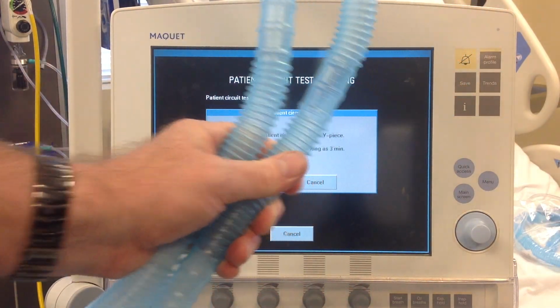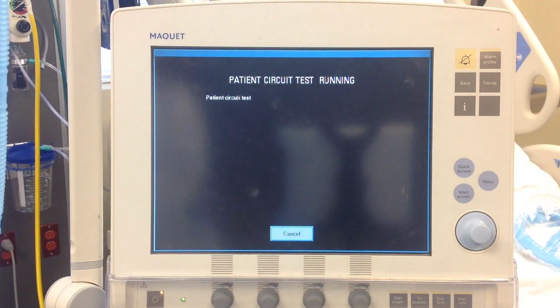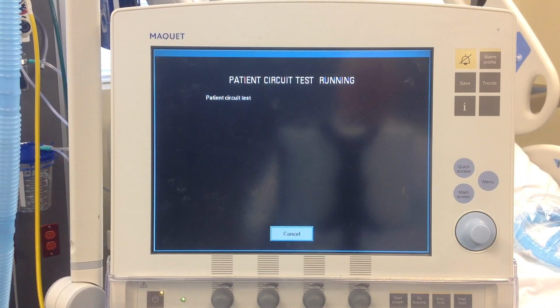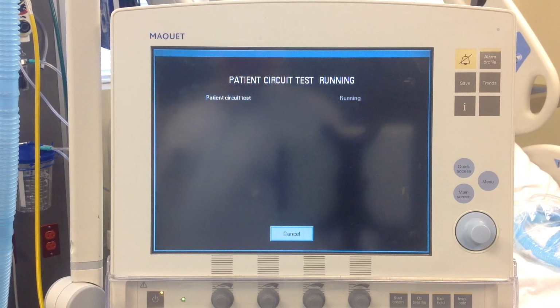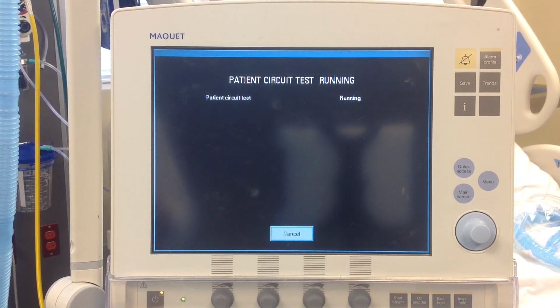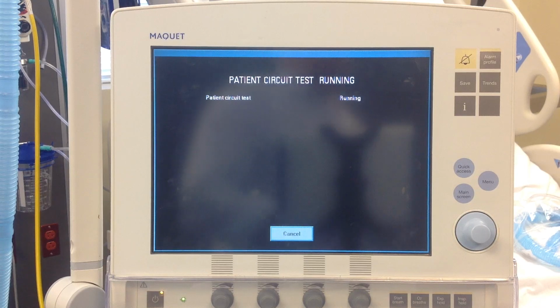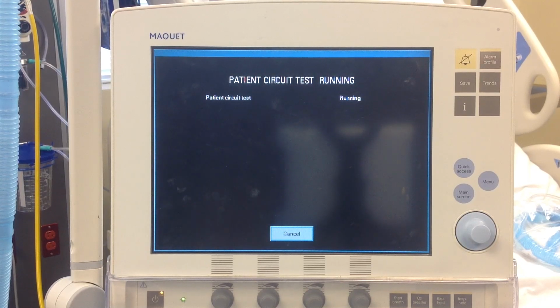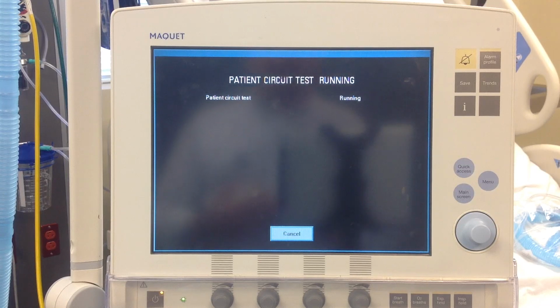The only one that the pre-use check or the patient circuit test has been completed on is the exact one that you put on. Even if you're putting the exact same circuit on, you will want to redo the patient circuit test. And this is only if you're staying on the same patient and you're changing the circuit on the same patient. You'll redo the circuit test because every circuit, even if they're the same kind, same make, same model, have different compressibility factors. And this is making sure that your patient gets the appropriate amount of volume. So this will take a couple minutes. And there's no way of speeding this up.